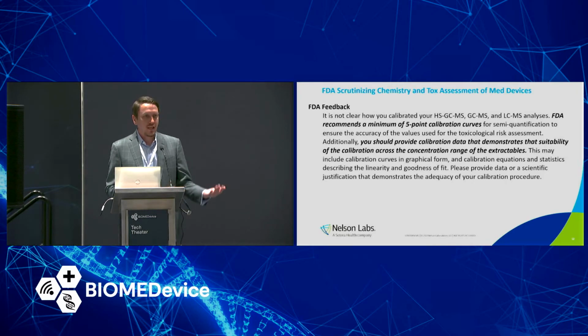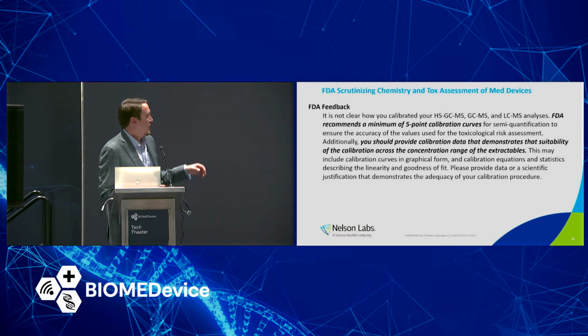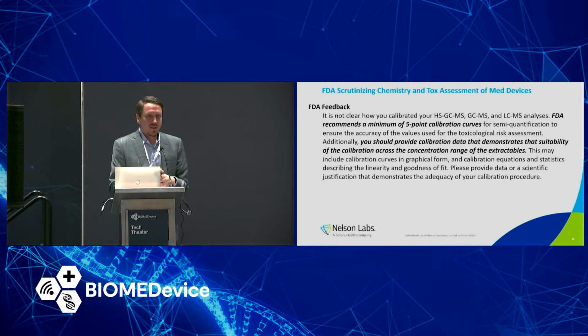It takes up many pages, but if you're going down this path, whatever lab you use should be ready to give this to the FDA if the FDA asks, or should just be providing it as an appendix to their chemistry reports. The way that this looks most often now is that when we talk about 5-point calibration curves, this corresponds to surrogates or internal standards that are part of each of those analyses. And for GCMS, it's usually a minimum of 3 surrogates or internal standards. It's not really a true internal standard, so I'm going to use surrogate. Minimum of 3 surrogates that have this criteria met, where there's a calibration curve.